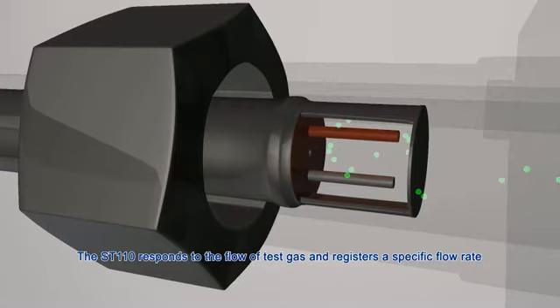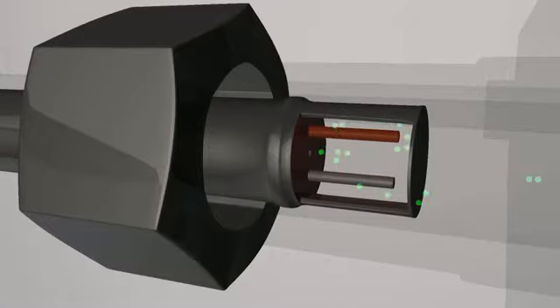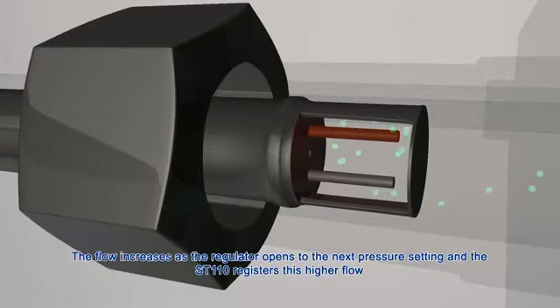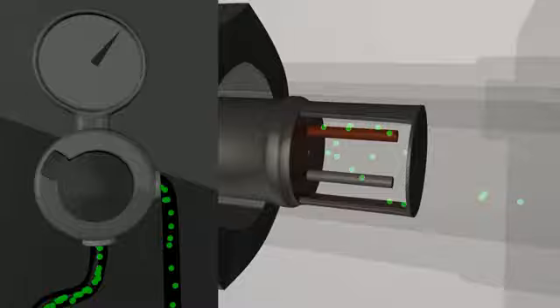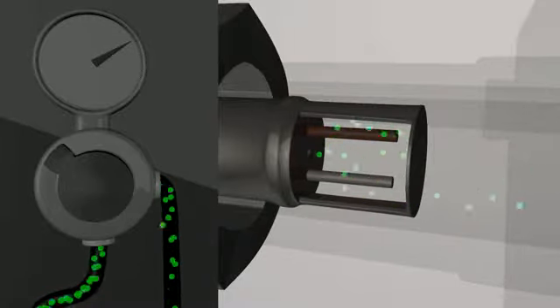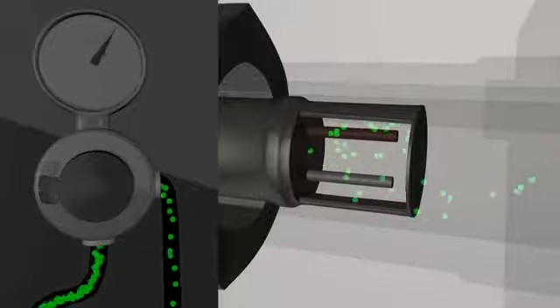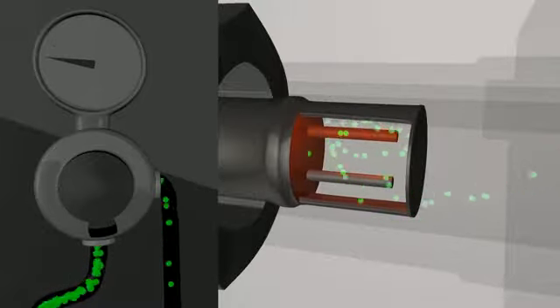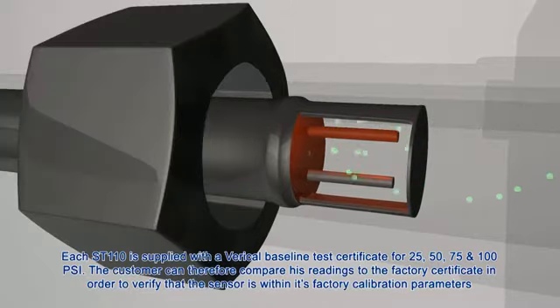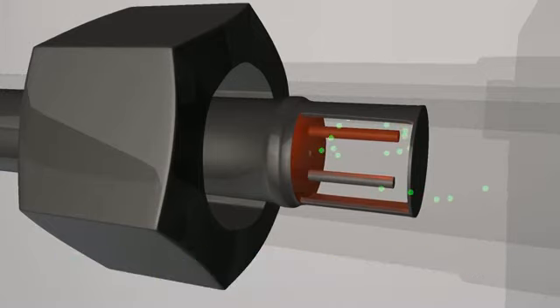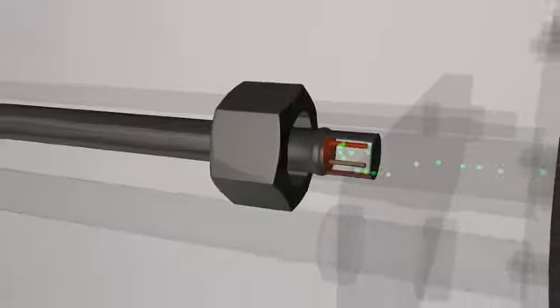The ST110 responds to the flow of test gas and registers a specific flow rate. The flow increases as the regulator opens to the next pressure setting, and the ST110 registers this higher flow. Each ST110 is supplied with a VeriCal baseline test certificate for 25, 50, 75, and 100 psi. The customer can therefore compare his readings to the factory certificate in order to verify that the sensor is within its factory calibration parameters.